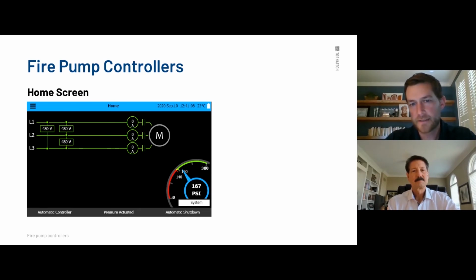You'll see the red line. It goes from 0 to 140. So 140 is the cut in pressure. Your system pressure right now is at 167, but if it happened to drop down below 140, it's going to come on. This pump, you can see here on the bottom, is an automatic controller. It's pressure actuated and it has the automatic shutdown enabled. So if the pressure drops below 140 PSI, which is the cut in point, the pump's going to start running.